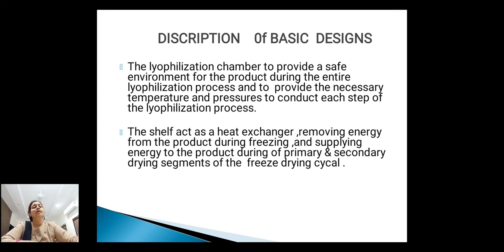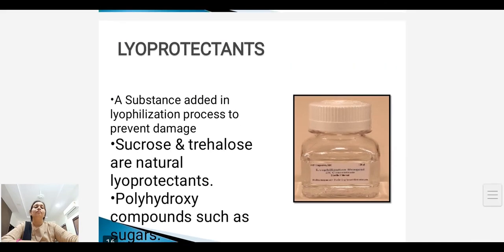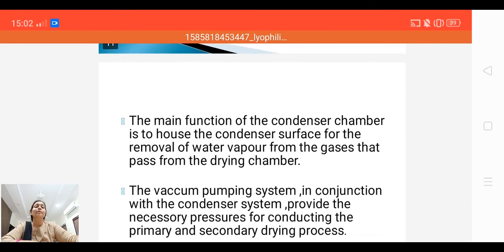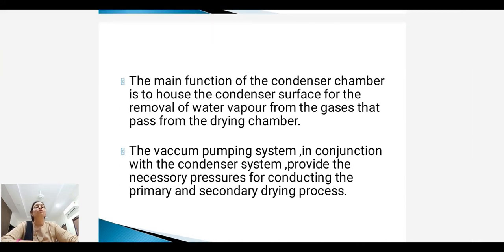The shelf acts as a heat exchanger, removing energy from the product during freezing and supplying energy to the product during primary and secondary drying segments of the freeze drying cycle. The main function of the condenser chamber is to house the condenser surface for the removal of water vapour from the gases that pass from the drying chamber. The vacuum pumping system, in conjunction with the condenser, provides the necessary pressure for conducting primary and secondary drying.